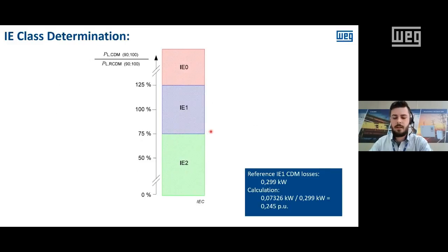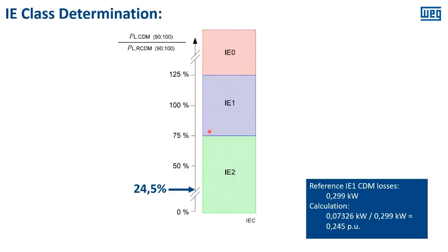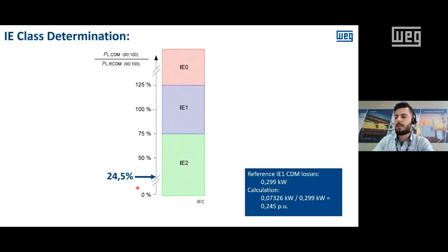To illustrate better how it is classified in the graph here, it's going to be here. So to achieve IE2, we should be at most 75% of the IE1 reference losses. And here we are at just 24.5% of the IE1 reference losses, which means we are much more efficient than IE2. There is no classification of IE3 until now, but if there were, it would probably be classified as IE3.